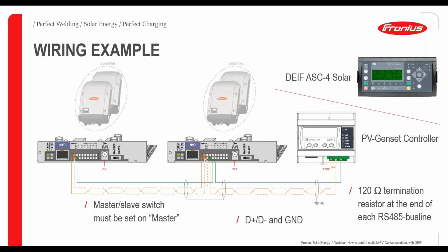There is a little dip switch above the antenna. Here we have then the ability to switch the termination to on. In the middle data manager, we need to set it to off. And again, end of our Modbus line is then on the controller in this case. And here we also need to set the 120 ohm resistor. So we need to make sure to do this. And in this case, then we have the perfect communication.